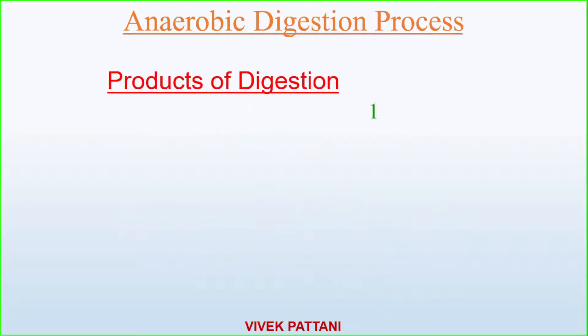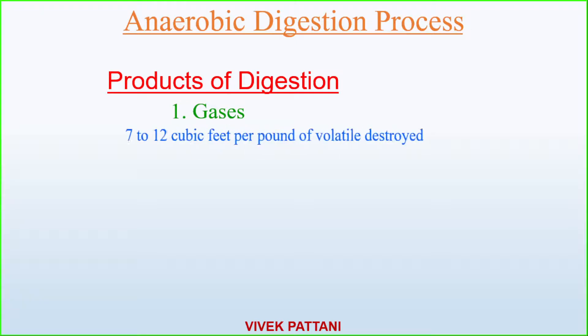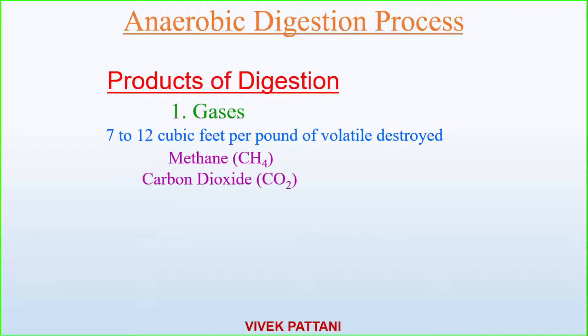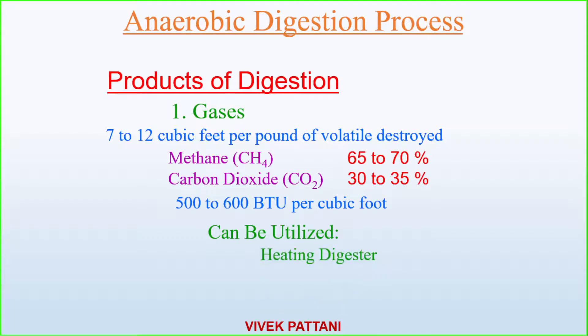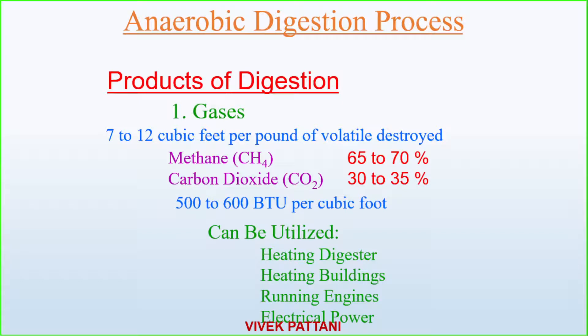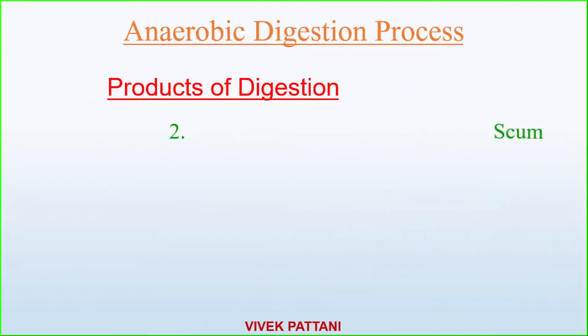The products of digestion include gases: approximately 7 to 12 cubic feet per pound of volatile solids destroyed. The gases are methane and carbon dioxide, of which methane is almost 65 to 70 percent and carbon dioxide is 30 to 35 percent, with an energy value of 500 to 600 BTU per cubic foot.